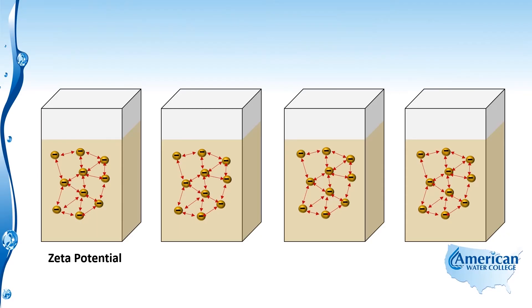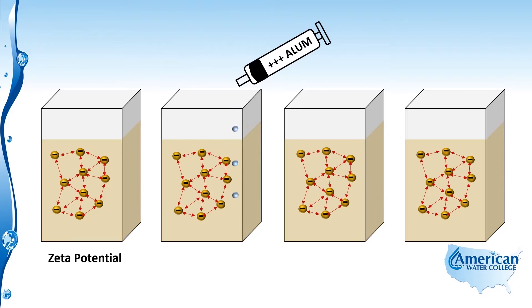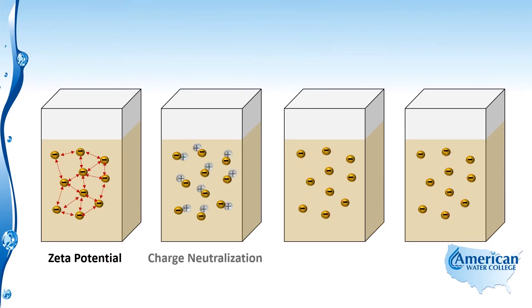In order to overcome that zeta potential so that these colloids can come together and form micro floc and then macro floc so that they can ultimately settle out, we need to neutralize the negative charge. We do that by the addition of positive ions. Aluminum sulfate — alum — is what we add here. When we add the alum, positive ions from the alum react with the negatively charged colloids and effectively neutralize the charge. We call that step charge neutralization.